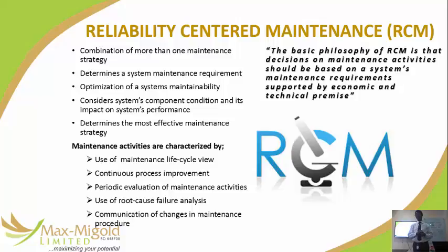intensive data collection. I have 4 generators. I must know how many liters of diesel each one runs, how much maintenance I spend, how many people I use to manage them, how much they earn. All of those must be at my fingertips for me to get the strategy right for reliability. So data and detail. If you think predictive was already data intensive, you've not started yet, because with reliability you are acquiring so much data.